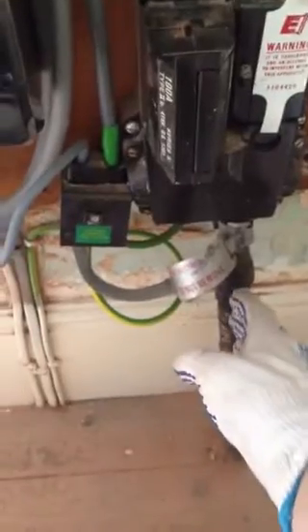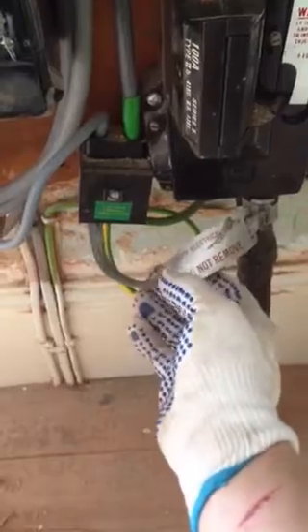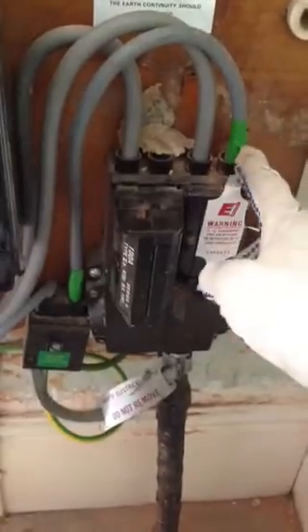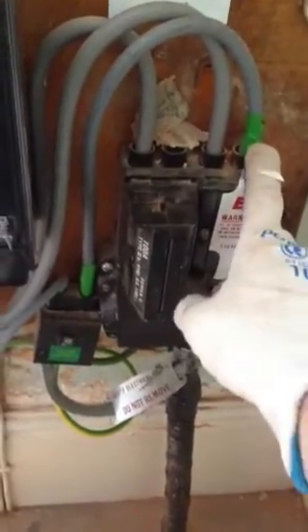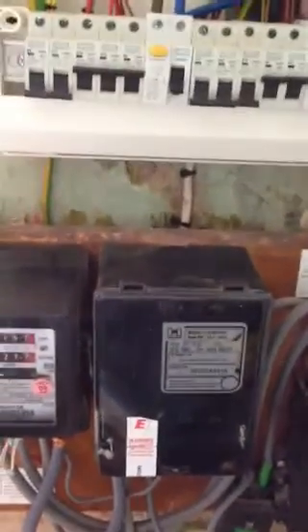Originally it was a TN-S system where the earthing was provided by the sheathing of the lead, and it has been changed, and you can see that this conductor here connects back to neutral, so it has been changed at some point to a PME or a TN-C-S earthing system.